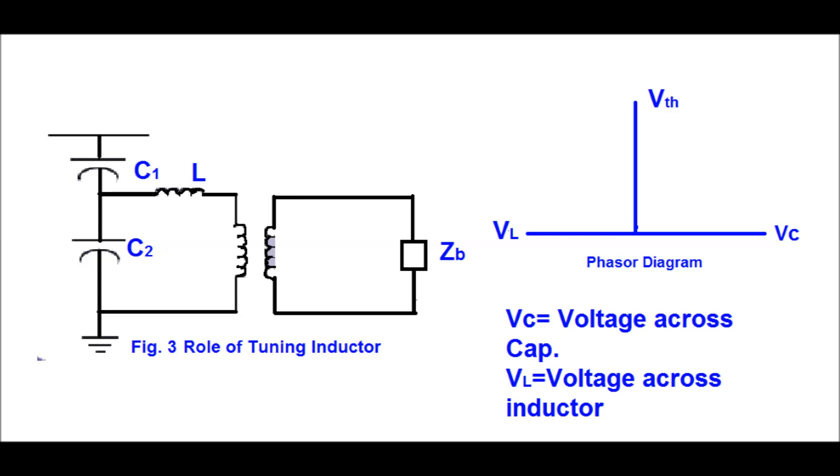The phasor diagram is shown in this figure. The value of the inductor is chosen so that it compensates for the net C at power frequency, which is 50 Hertz in India.